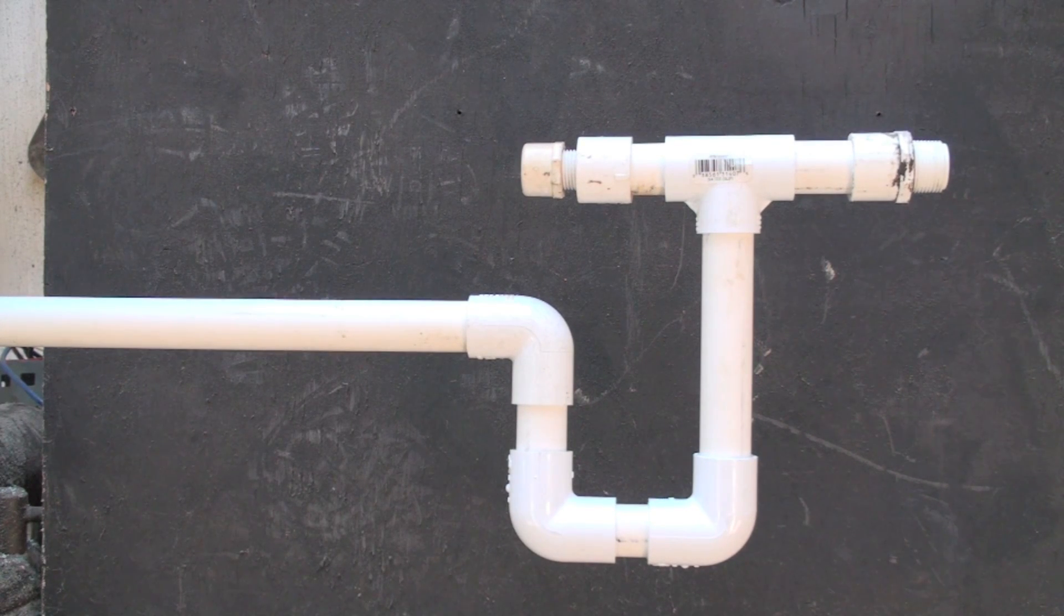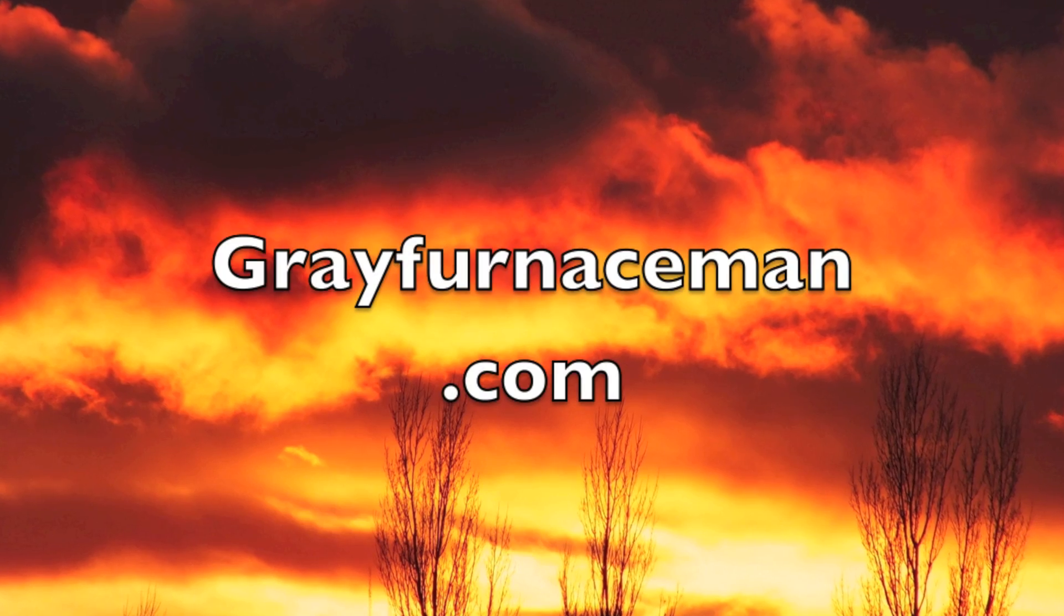I hope this helps in designing these P-traps. If you don't put a P-trap in, a lot of times you'll get water on the floor. Or if it's a rooftop unit, it'll actually dump water down the ductwork. So they are important because it's going to suck that condensate back in and throw it everywhere. Thank you.